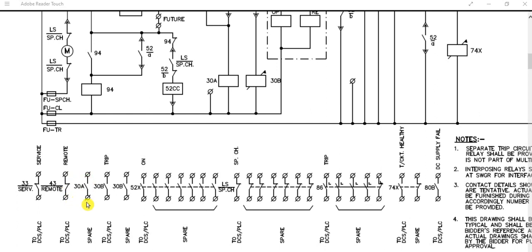There are spare contacts for 30A and 30B. 30B is the trip contact, also going for indication purposes. Some spare contacts are made available for future activities and future expansion. The main circuit breaker auxiliary contacts are available here — only one contact is used for DCS or PLC communication, the circuit breaker ON status. The remaining auxiliary contacts are kept as spare for future use.